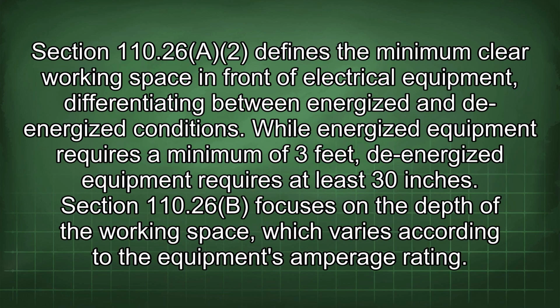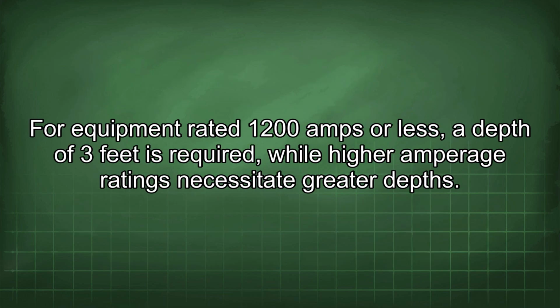Section 110.26(a) defines the minimum clear working space in front of electrical equipment, differentiating between energized and de-energized conditions. While energized equipment requires a minimum of 3 feet, de-energized equipment requires at least 30 inches. Section 110.26(b) focuses on the depth of the working space, which varies according to the equipment's amperage rating. For equipment rated 1200 amps or less, a depth of 3 feet is required, while higher amperage ratings necessitate greater depths.